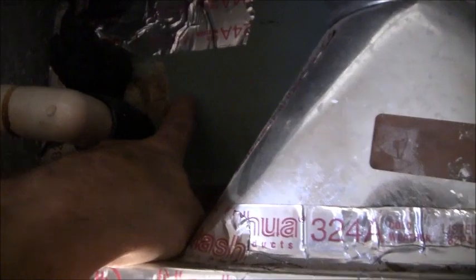Now, on modern units, they have two drain lines. The primary, and then at a higher elevation, a secondary. You're supposed to put a float switch in there. If the primary backs up, it goes to the secondary drain line, and then the float switch gets activated, shuts it off.